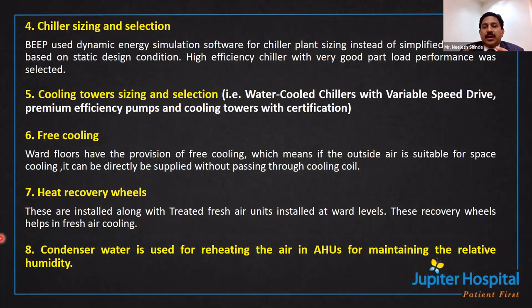Those in the medical equipment field understand that for medical equipment, humidity is very important. Everyone says it has to be below 60%. To maintain it below 60%, there are a couple of things you can do. One is what we did in our first properties, we put electrical strips to maintain humidity, but it costs a huge amount. Against that, if you do a hot water coil, and with the help of condenser water or a heat pump supply hot water there, it gives a huge reduction in energy consumption.